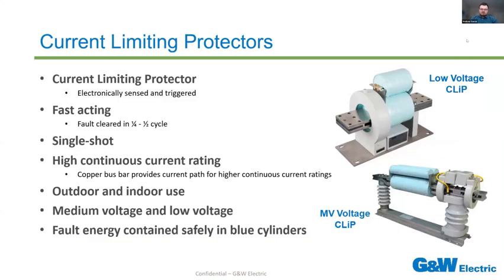So going over specifically on the current limiting protector, you can call it CLIP. It is an electronically sensed and triggered device. You do need the electronics in order to trigger those pyrotechnics. It ends up being a fancy copper bus bar without the electronics. It is a fast-acting device, clears that fault in 1/4 to 1/2 an electrical cycle. That being said, it is a single shot device.